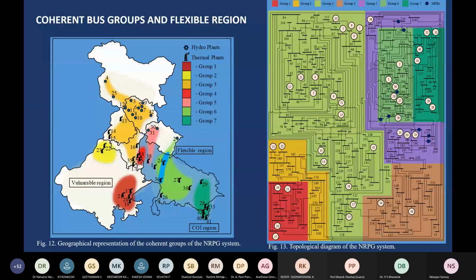On the left hand side you see the map of India, particularly the northern grid, and we divided all the generators. We had about 240 generators in the system, and those 240 generators are divided into 7 groups, each group behaving in a similar fashion. The line diagram on the right corresponds to the geographical location on the left. And here you can see that the center of inertia has been identified to lie in eastern UP.